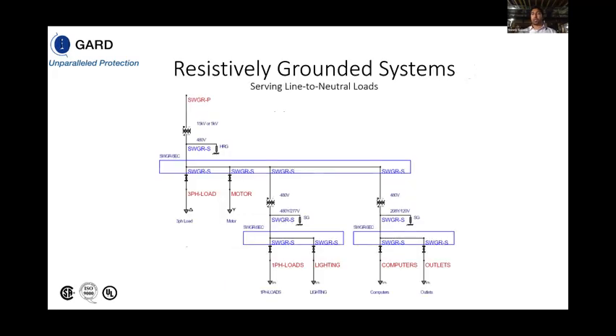Now, here's an example of how we utilize single phase loads on a resistance grounded system. At the top section, we have a high resistance grounded 480 volt system, which is 3-phase 3-wire, handling 3-phase loads such as motors. And then we've placed these 2 isolation transformers here to convert the system from high resistance grounding back to solidly grounded, where we can now have that distributed neutral to satisfy single phase loads such as lighting. In addition to that, for the loads at 208, 120, we can satisfy that by also going to solidly grounded and satisfy computers and outlets that are most commonly utilized.